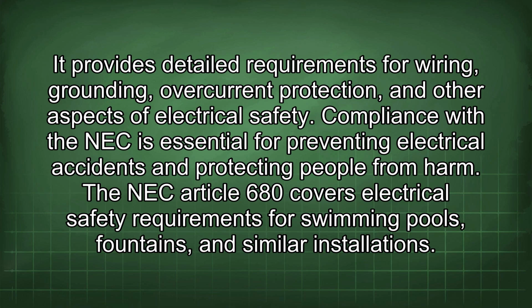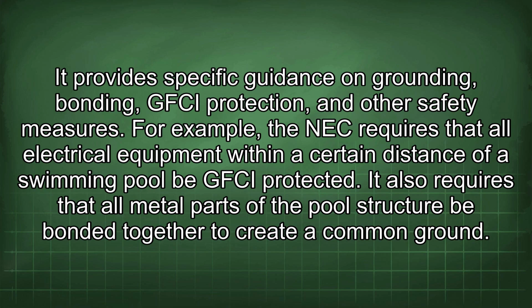The NEC Article 680 covers electrical safety requirements for swimming pools, fountains, and similar installations. It provides specific guidance on grounding, bonding, GFCI protection, and other safety measures. For example, the NEC requires that all electrical equipment within a certain distance of a swimming pool be GFCI protected. It also requires that all metal parts of the pool structure be bonded together to create a common ground.